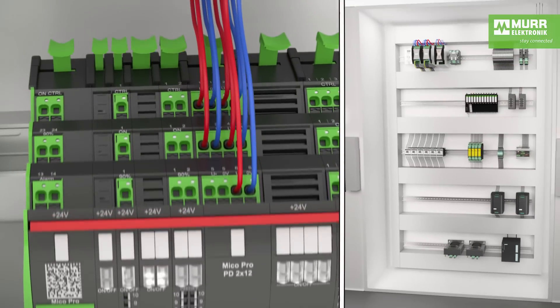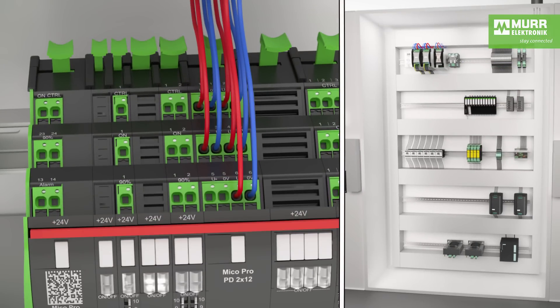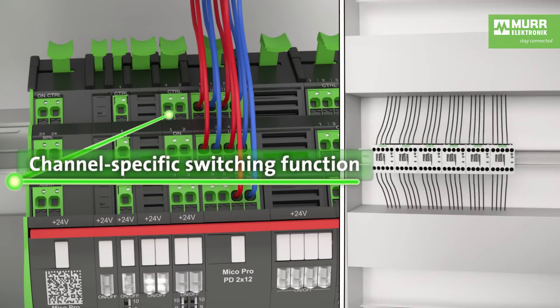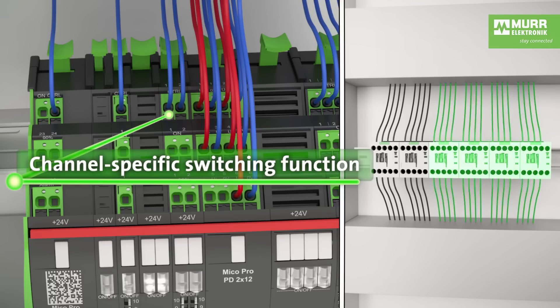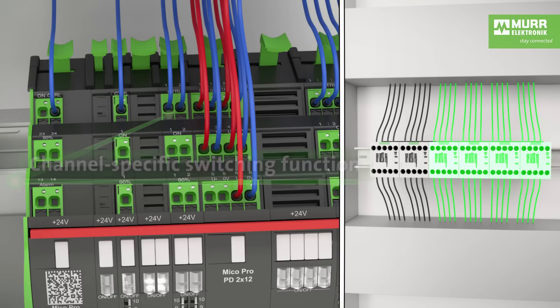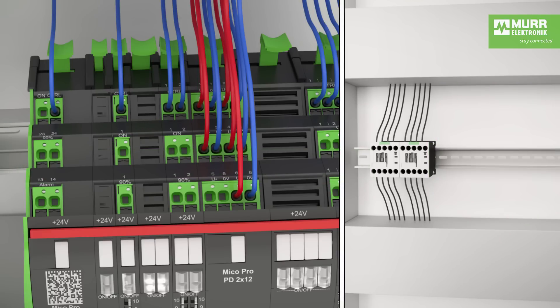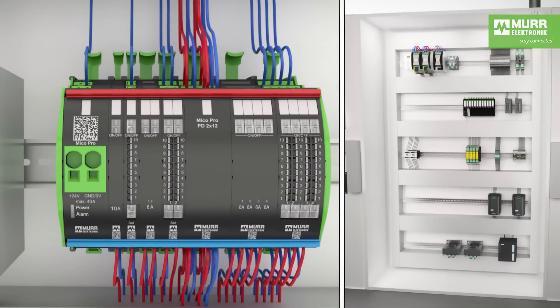A channel-specific switching function allows the flex modules to switch system components on and off via a PLC signal, without any additional contactors, relays, or optocouplers. This feature reduces a large portion of the coupling and switching level in a cabinet. All these functions significantly declutter the switch cabinet wiring and save a lot of space.